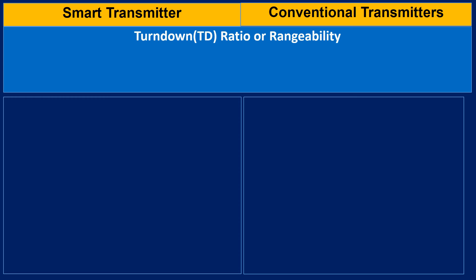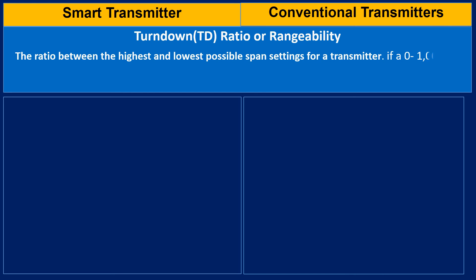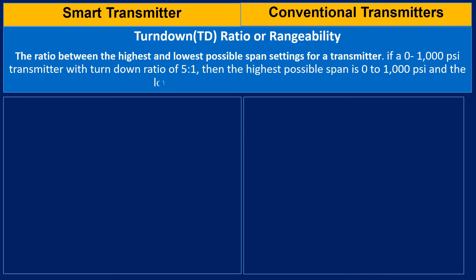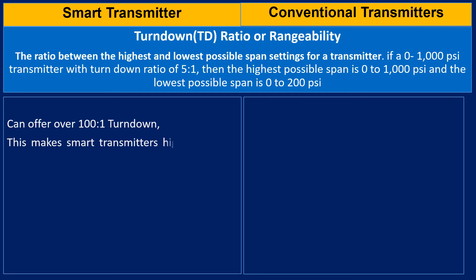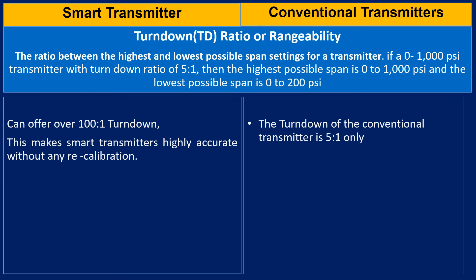Comparing both transmitters in terms of turndown ratio: the turndown ratio is the ratio between the highest and lowest possible span setting for a transmitter. For example, if you have a 0 to 1000 PSI pressure transmitter with a turndown ratio of 5:1, then the highest possible span will be 0 to 1000 PSI and the lowest possible span can be 0 to 200 PSI. Smart transmitters can offer over 100:1 turndown ratio, making the pressure transmitter highly accurate without any recalibration. The turndown ratio of a conventional transmitter is 5:1 only.